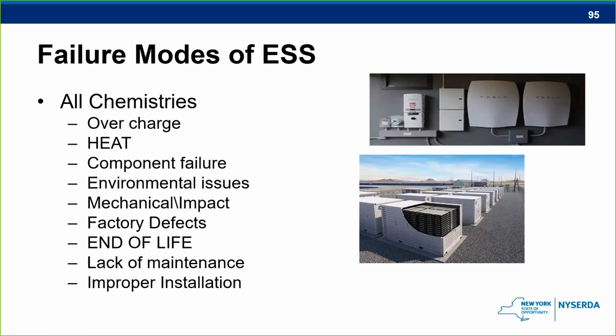Component failures is another thing. Responders are not familiar with these things, very technical subject. So they don't even know some of the components, but if there was a problem with the BMS, which was mentioned before, that could cause an overcharge or cause a heat or some other failure from taking place. So those components have to be listed in some cases, like the inverters that she had mentioned before, Jennifer mentioned before about the different listings for the product itself.